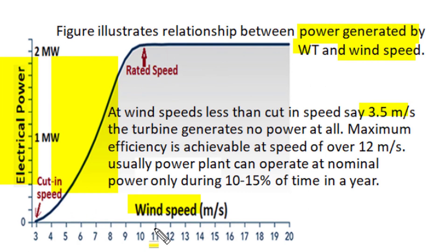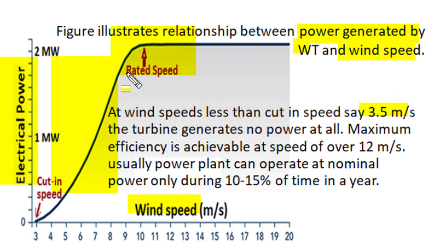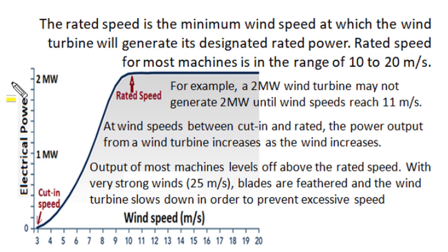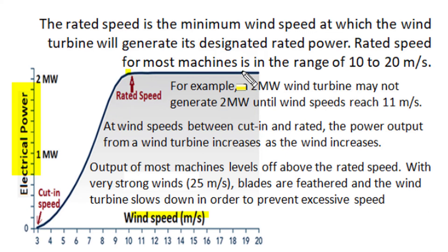The maximum efficient electric output is achieved at a wind speed of around 11 or 12 meters per second. Usually, wind power plants can be operated at such optimum wind speed conditions only 10 to 15 percent of the time in a year, as most of the time wind speeds are less than this ideal condition, and sometimes wind speed can become extremely high too. In the electric power output and wind speed relationship, rated speed is the minimum speed at which a wind turbine will generate its designated rated power — typically between 10 to 20 meters per second for the majority of wind turbine machines.